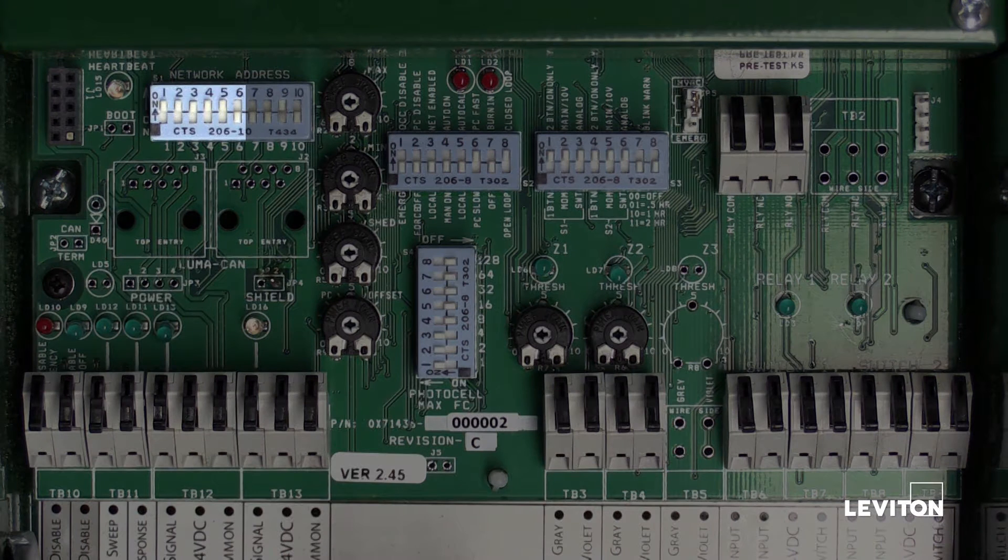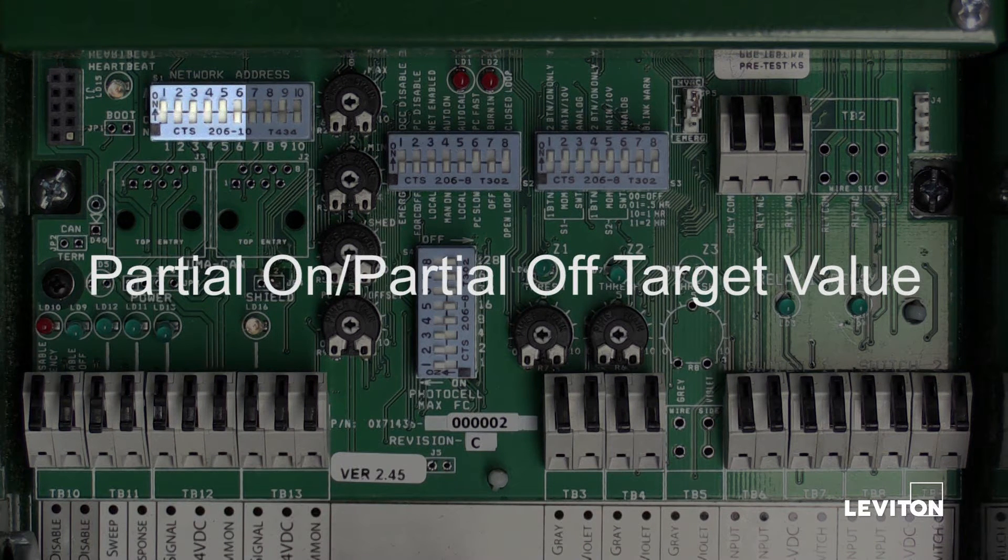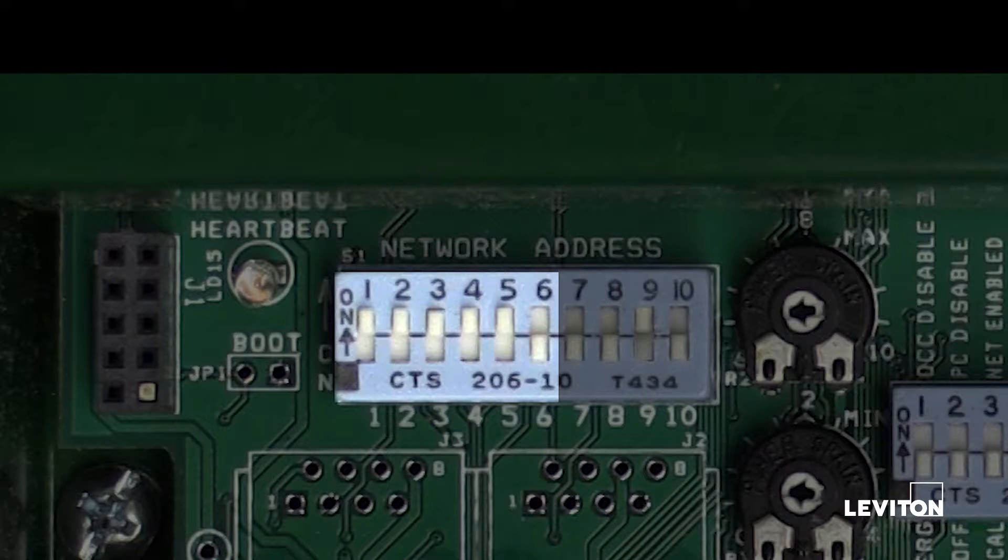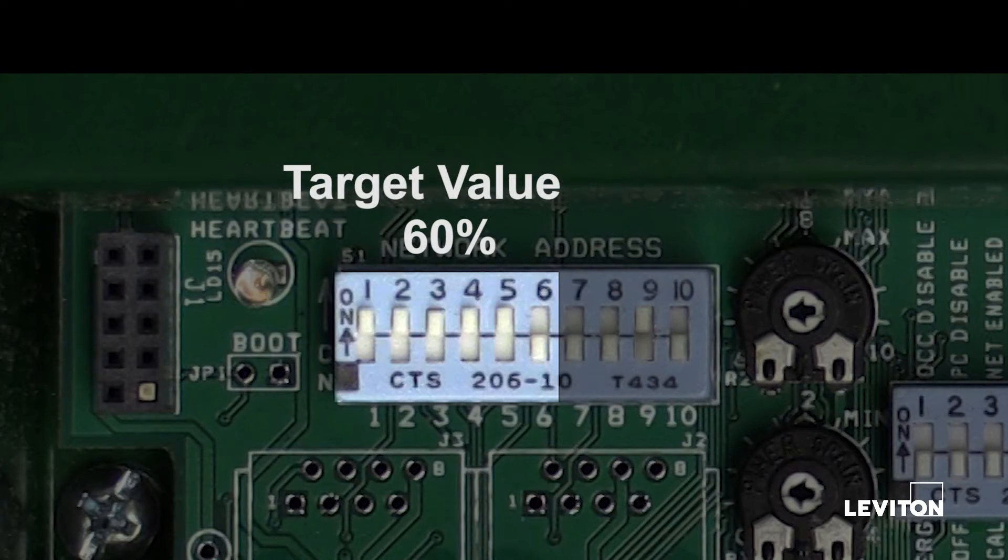Dipswitches 1-6 are used to calculate the partial on or partial off target value associated with the occupancy sensor. Each dipswitch in the on position adds a value of 10% to the total count with a maximum value of 60%.